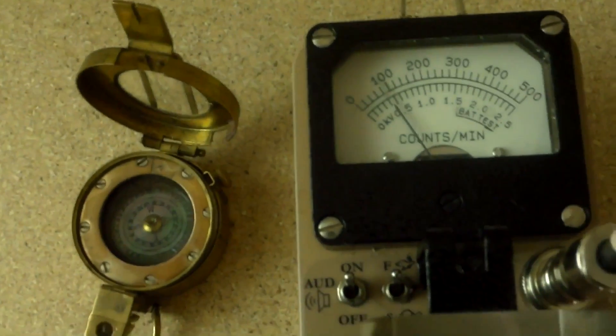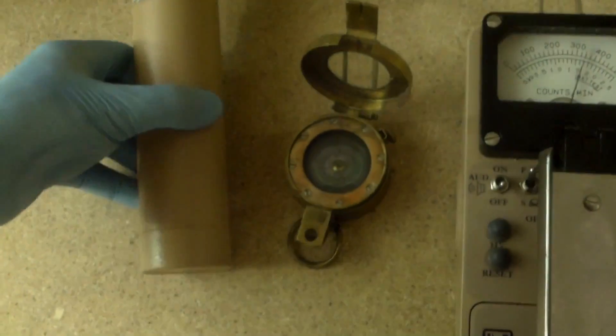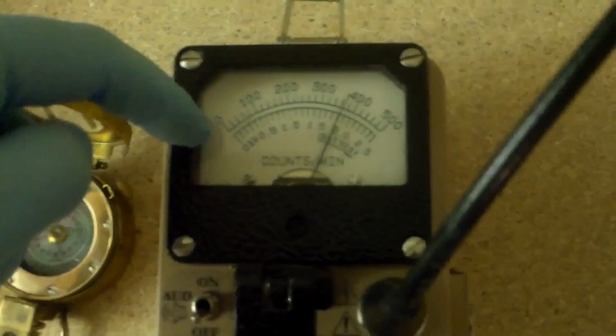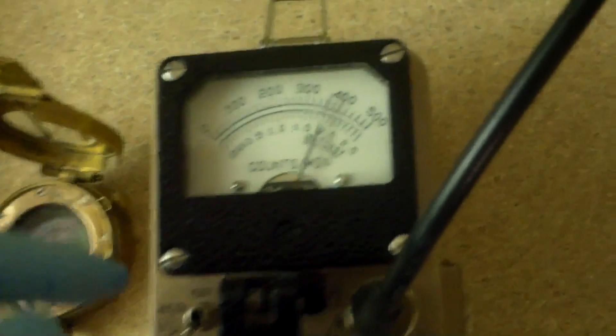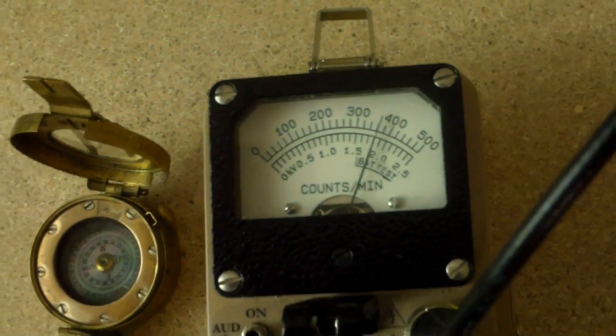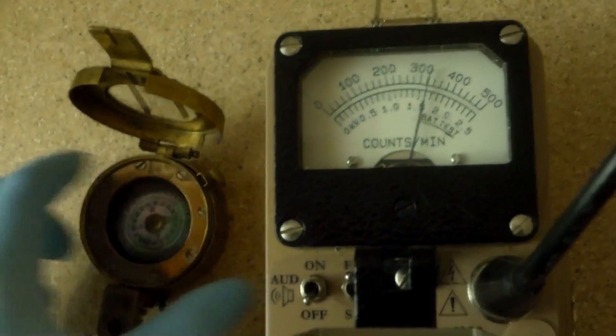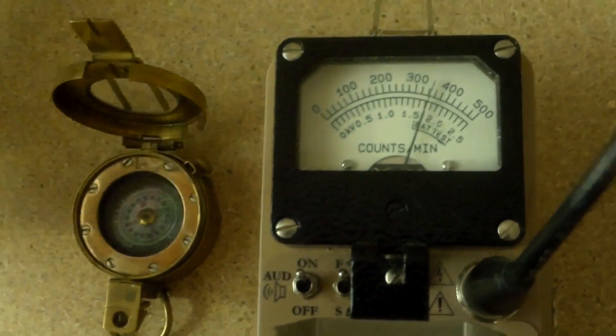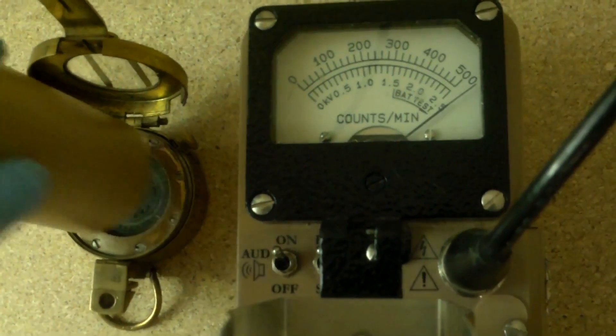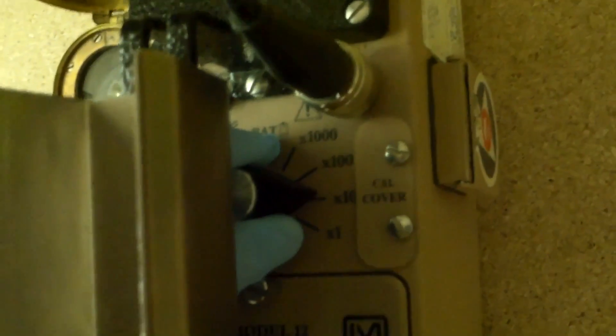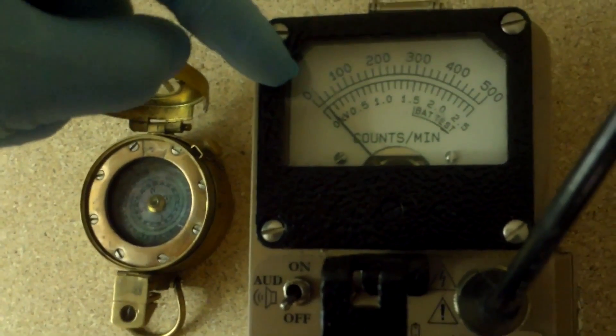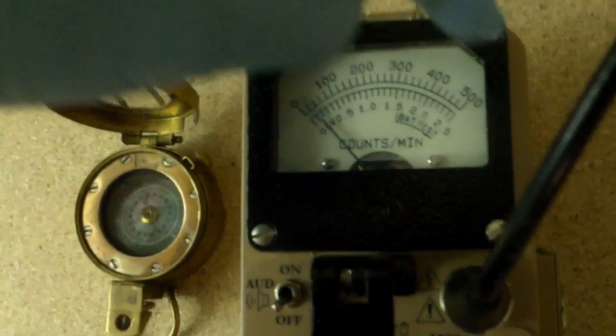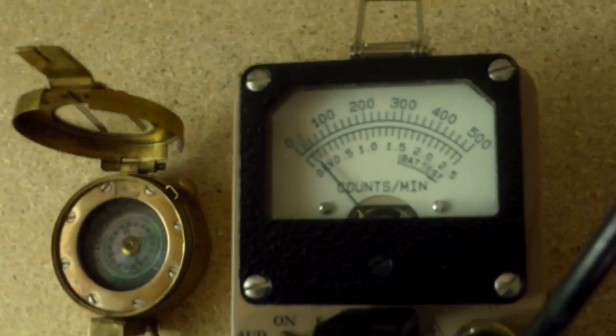Alright, now I have a 1-inch sodium iodide probe connected to it. And as you can see on our scale, we're on times 10 again, so it's 0 to 5,000 counts per minute. And our background right here is sitting around maybe 3,500 counts per minute. We put this near it, and we go hard over. So let's cut the sound off and switch this thing to times 100. So now we're at 0, 10,000, 20,000, 30,000, 40,000, 50,000 counts per minute. This is in counts per minute.